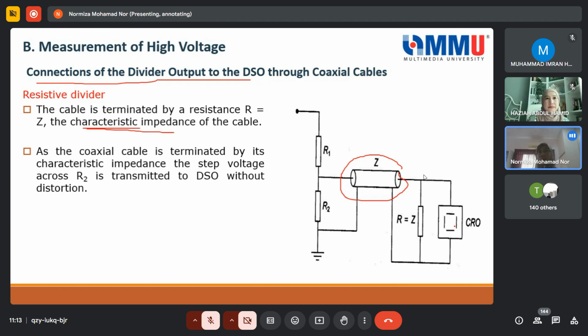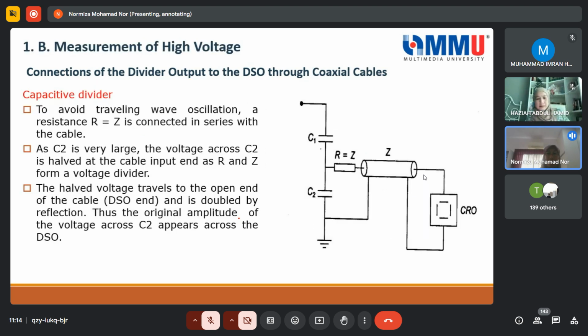But for the current measurement, which I didn't put in the slides, you may experience that the current may be doubled, or the current may be half, on the oscilloscope. For example, the current is 10 kilo amp, but on the oscilloscope after you convert it, it becomes less than 10 kilo amp. That can also happen because of the cable impedance characteristic. But it's not covered in this lecture, because that one we do for the testing, which is another chapter at MMU.